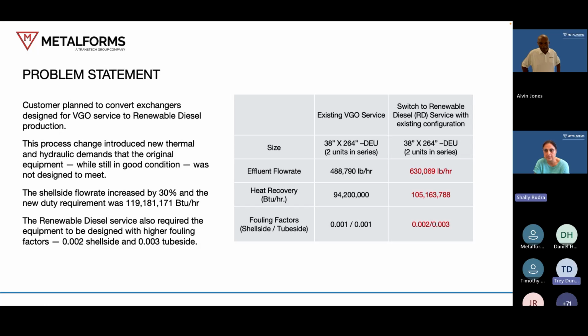The initial assessment was that the customer planned to change the application of the existing heat exchangers from VGO to renewable diesel. The challenge was a large throughput that was going to be put through the shell side of these exchangers. The initial assessment showed that if they kept the existing exchangers, they would only be able to meet 86% of the new duty requirements, mainly due to higher throughput, and because the service itself made the design prone to higher fouling factors.